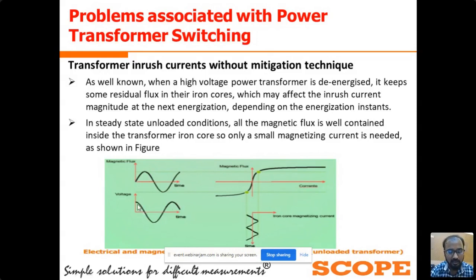As we know, the voltage and the magnetic flux are the integral of each other. Means whenever the system voltage is at peak, the magnetic flux is near to its minimum point. So here you can see the system voltage is at peak, and at this point the magnetic flux is near to its minimum point. So the main cause of the high inrush during the energization of a power transformer is the residual flux available in the power transformer core.